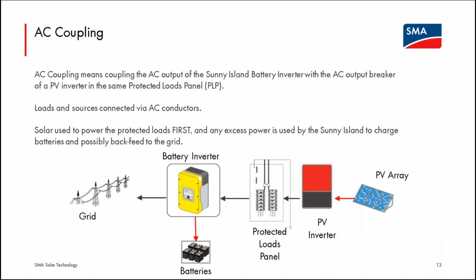And so we're showing the protected loads panel in the middle between the Sunny Island and the PV inverter. Again, in grid tie mode, the Sunny Island by default will allow excess PV power. If there's more than the loads need, more than the Sunny Island needs to charge its batteries, the excess will be allowed to backfeed to the grid. But that is a user adjustable parameter that can be set to 0 or turned off so that there is no grid backfeed depending on what the utility may require.